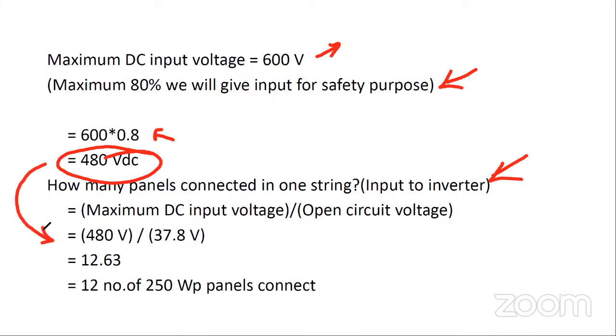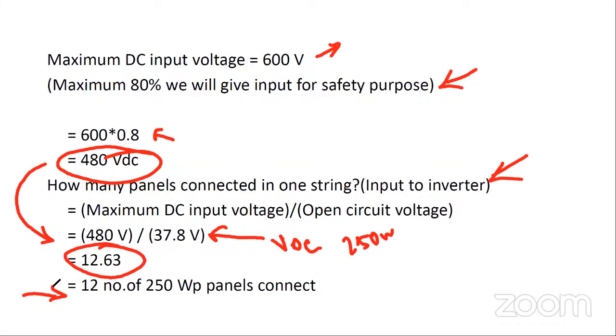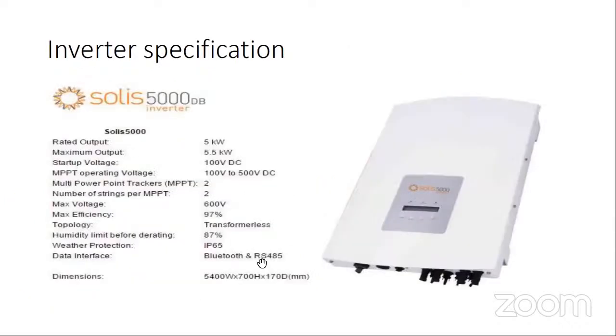That is divided by 37.8, the VOC of the 250 watt PV module. If you divide, the figure is 12.63. So basically 12 panels of 250 watts can be connected in one string comfortably to the inverter. As we already know, the number of strings for the inverter is 2.